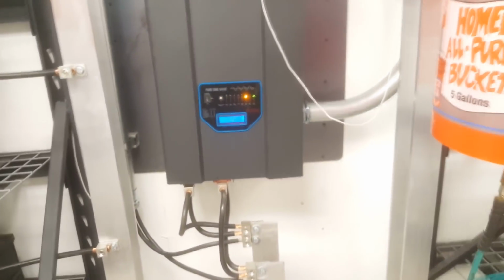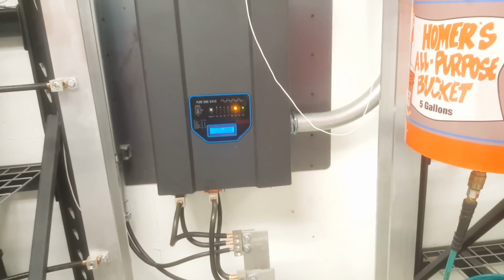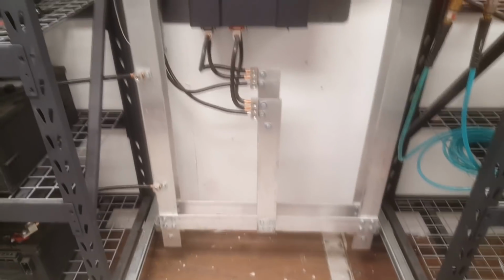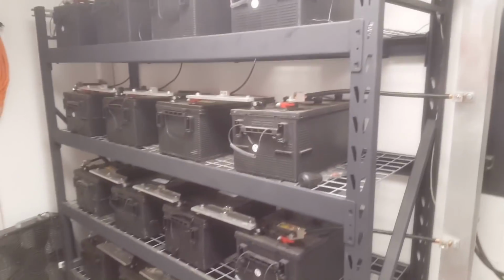I think I can get it. There we go. Now it's at full bore, but it's not because it's in absorb mode and this is a constant voltage, not constant current. And you can see the output voltage on these charge controllers has gone up. That's now charging the batteries through the bus bars and through the connections.